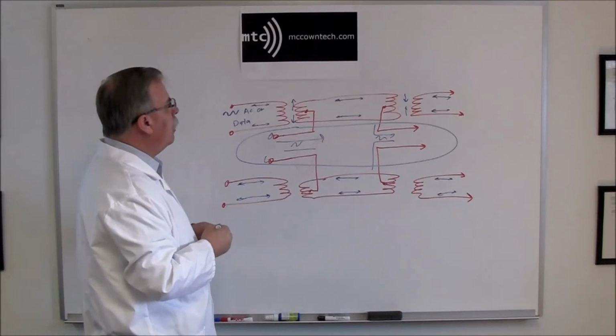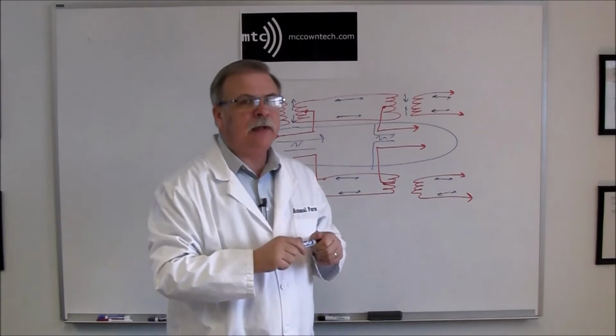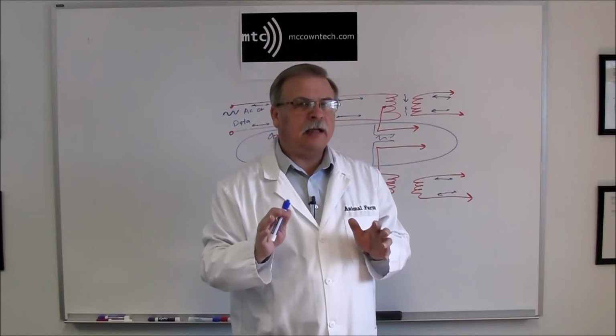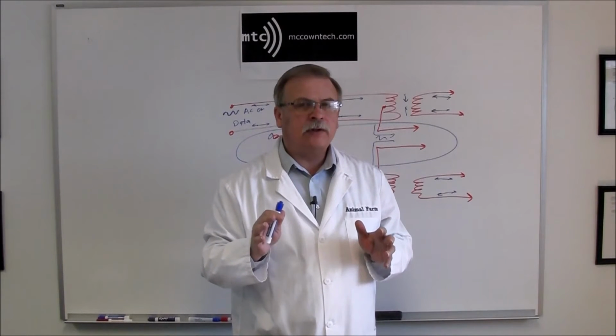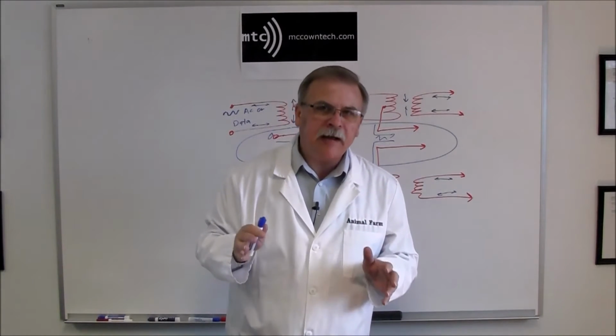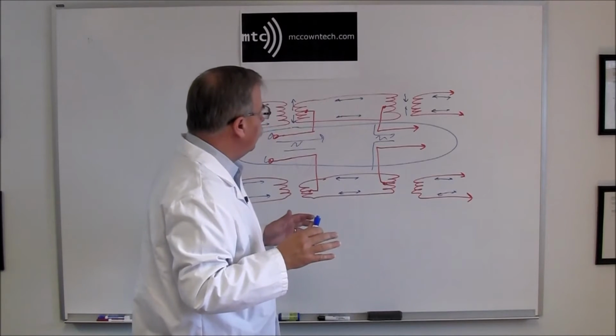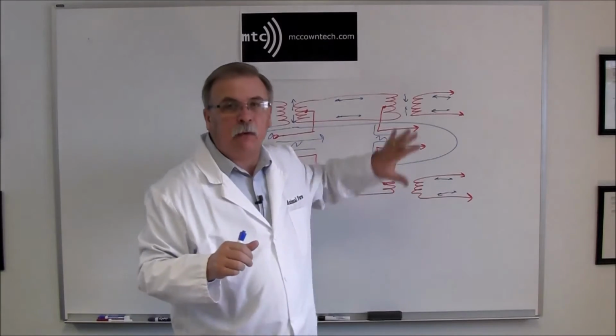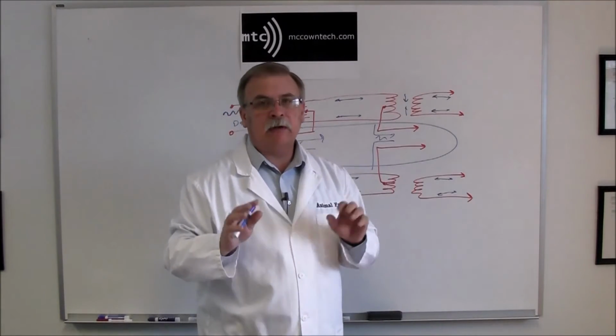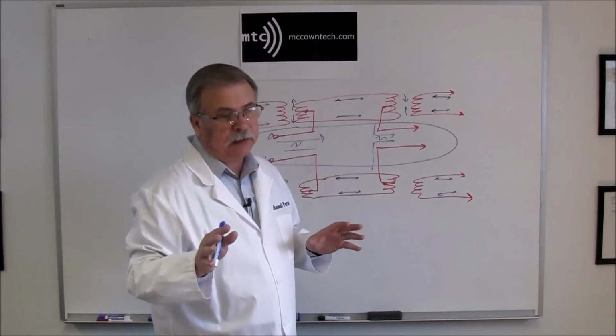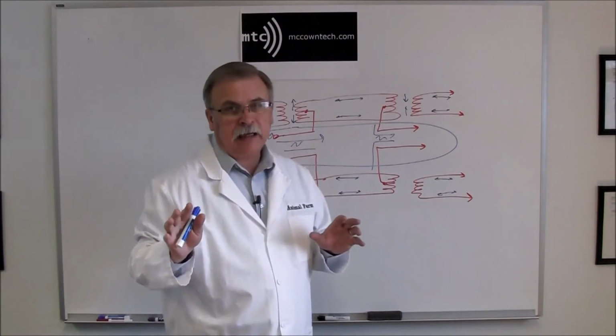Phantom circuit — this is exactly what we're doing with GigE POE. We're just running the power over the phantom circuit. And we've got 8 wires, so we can have 4 sets of this, and we can run a lot of power over it, relatively speaking. Let me get to that in just a second here.